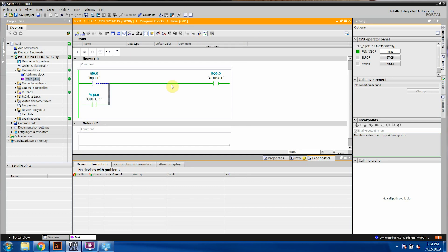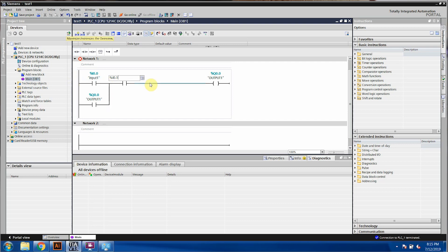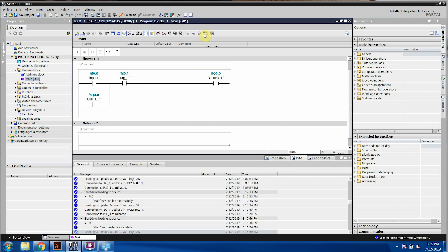How to sort it out? We have to go back to normal programming mode and add something here. We are going to use another push button — I0.1. This is our stop. Remember we discussed I0.1 which is coming from the normally closed contact, so I'm gonna take a normally open contact of that into the programming. This is going to act as the stop bit — this one is now start and this is stop. Our program is ready and I'm just gonna download this project.